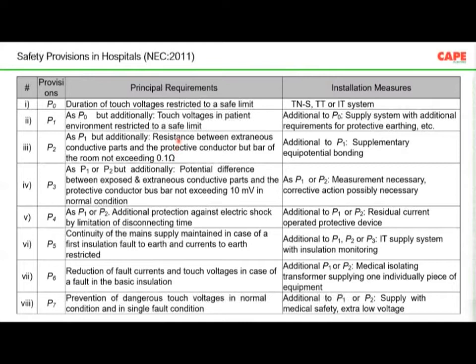But how to measure this is also equally important. If you take a multimeter and measure the continuity resistance, of course, you get erratic values. You have to have a very good, high quality micro ohm meter to make this particular measurement. Then P3, I don't want to read much into it. So different protective measures and provisions are recommended in the National Electrical Code 2011.